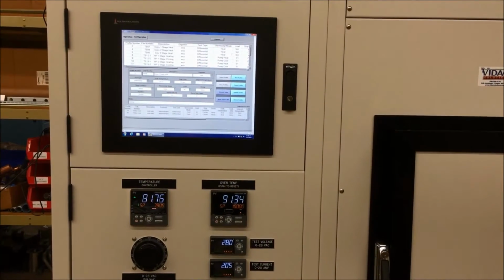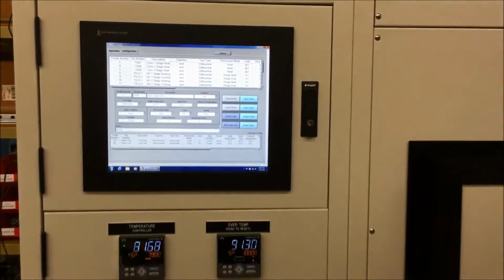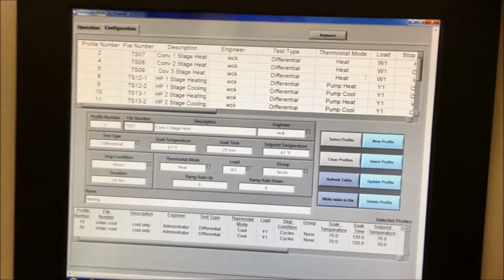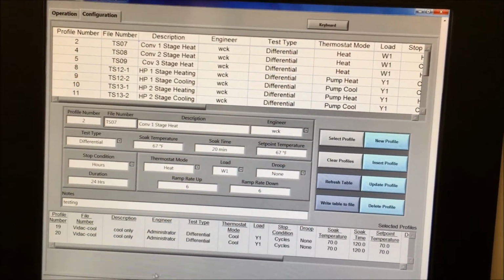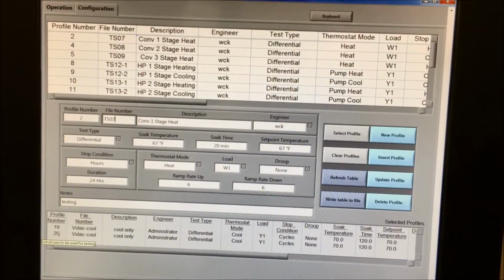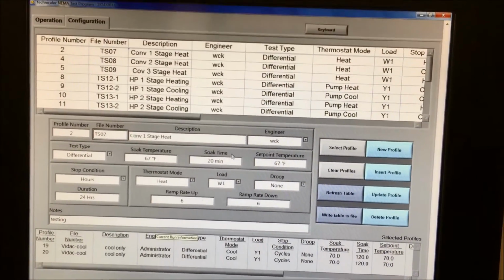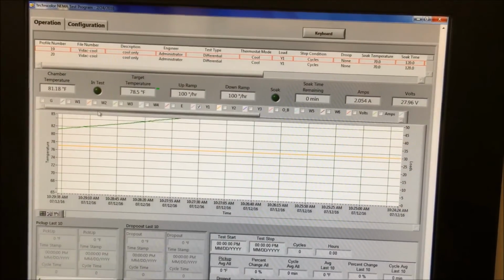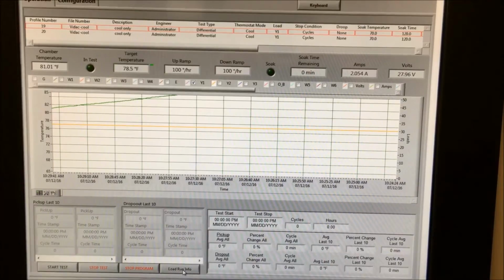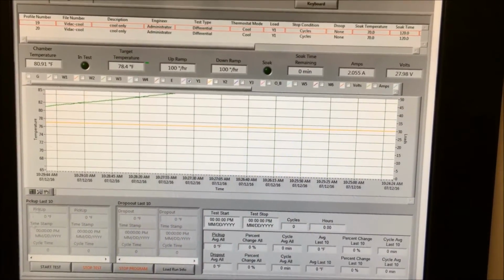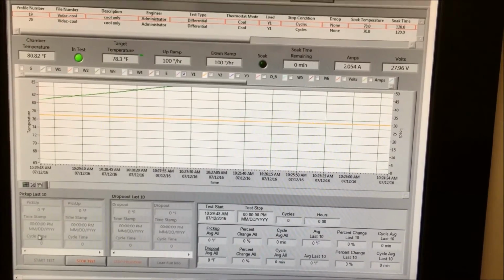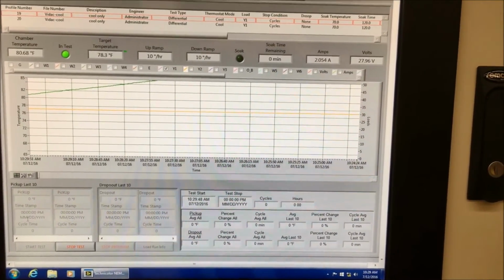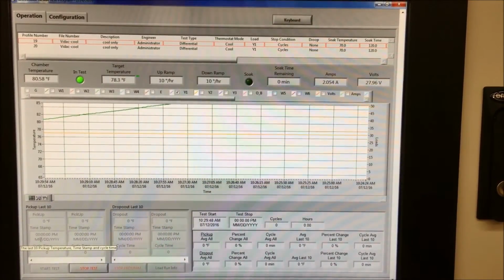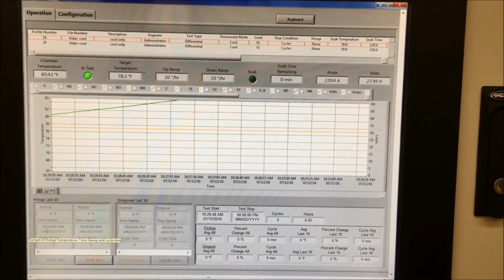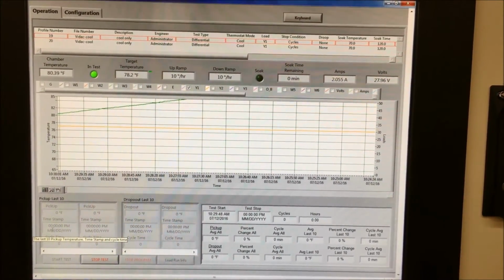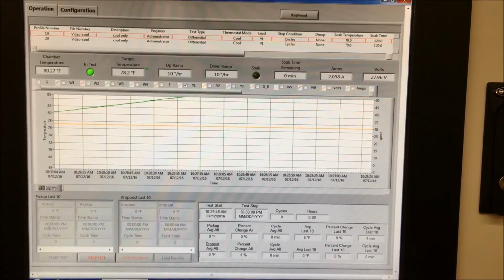To operate a test, which the box is currently coming down from 100 degrees, we've added a thermostat, and we're going to select to run 19 and 20 from the profiles, which are both cooling tests. We'll go to operation. We load the run information, which puts it at the top, and we'll start the test. Its current set point is going to be at 70 degrees because that's what we've set the soak temperature to, which you can see at the top. Once it reaches 70 degrees, it'll soak for 120 minutes, and we'll start the test.